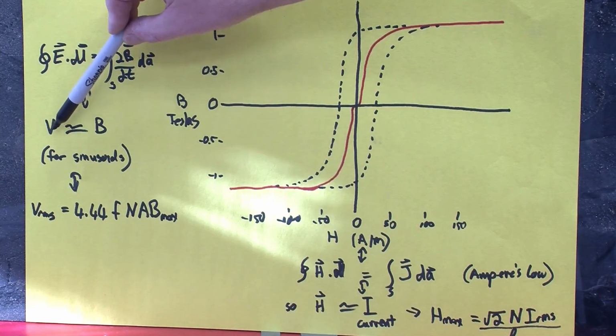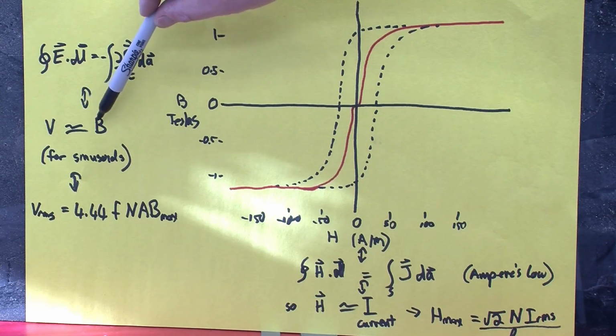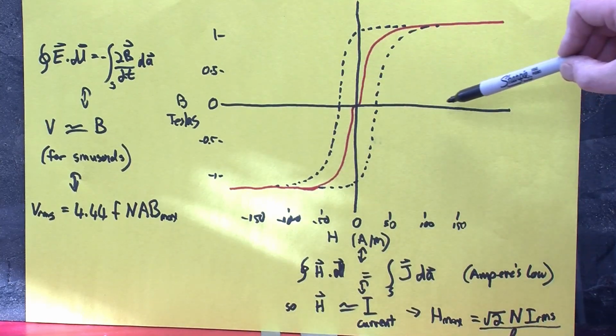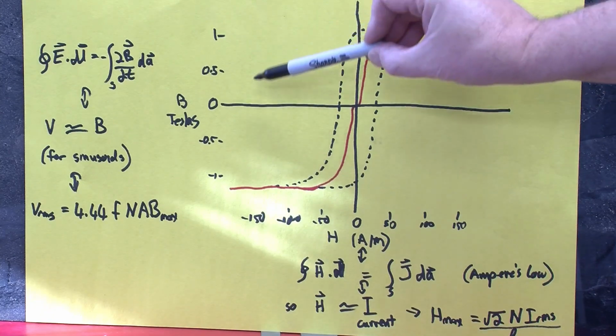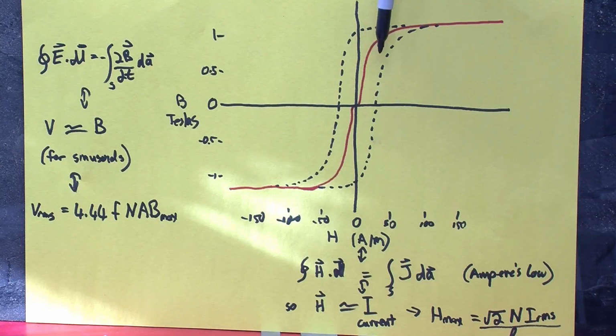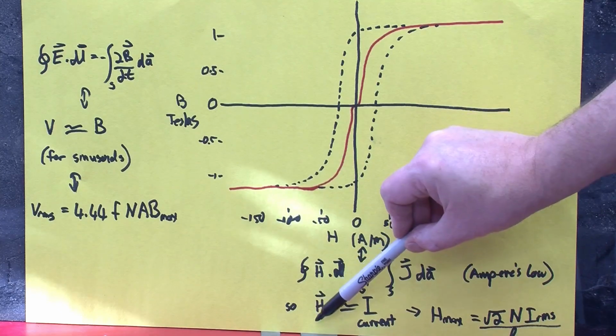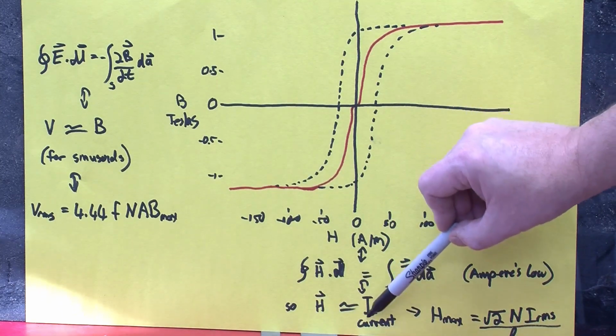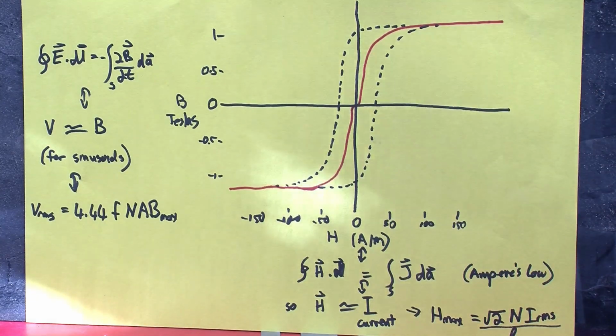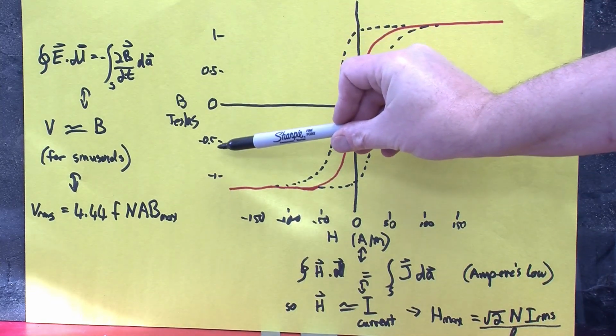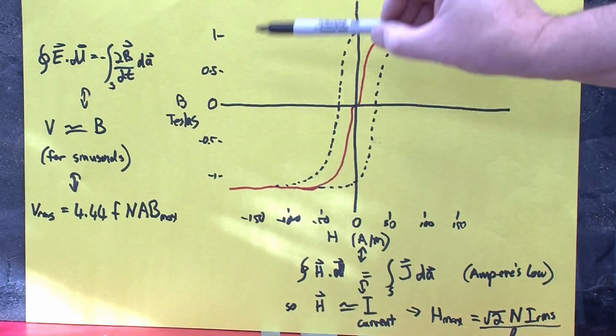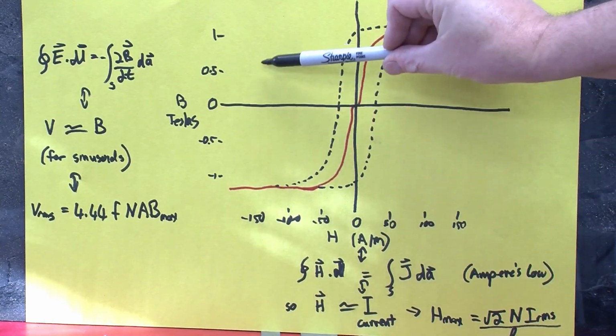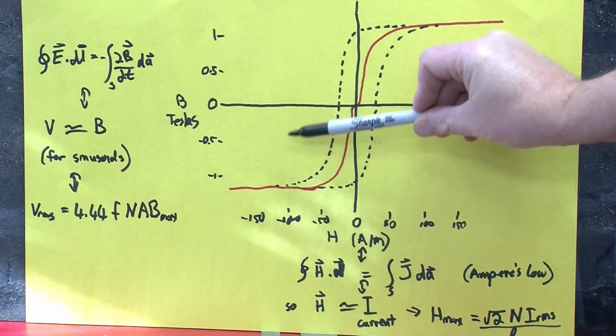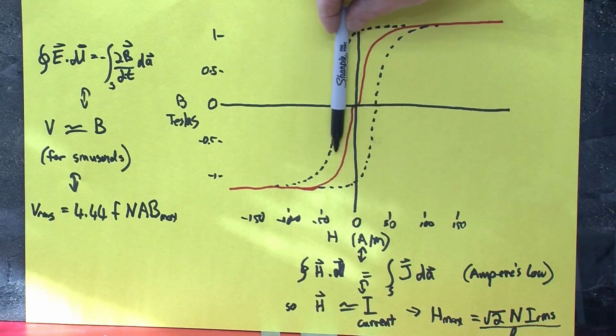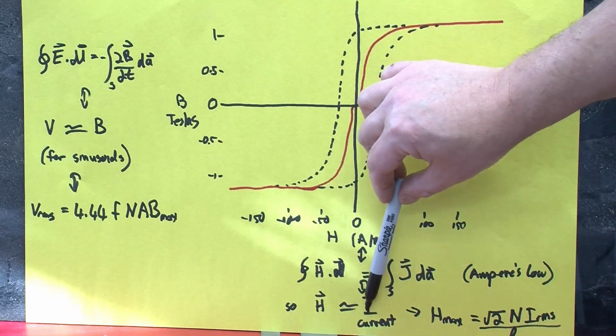So we can say the voltage we see is in some way proportional to the B field. This graph shows the properties of the steel core, relating the B field in Teslas to the magnetic force field H, which is almost directly related to the current running in the wires around the core. When we apply a voltage, it's really the derivative of the B field, but we'll just call it the voltage, and that voltage swings up and down. This graph maps that to the required H field going up and down, and that H field maps to current.